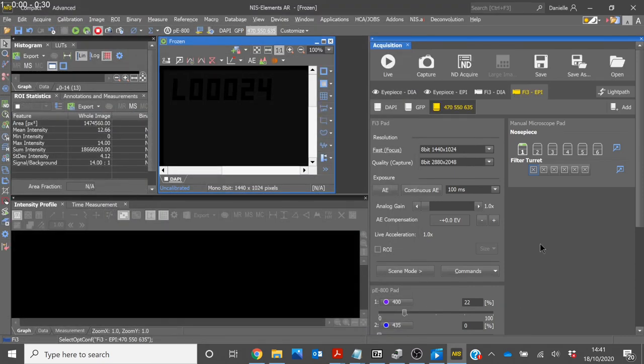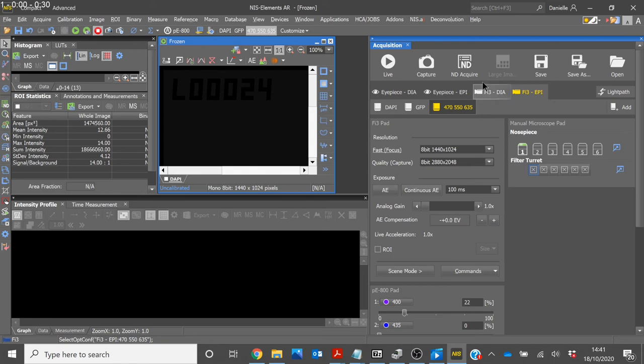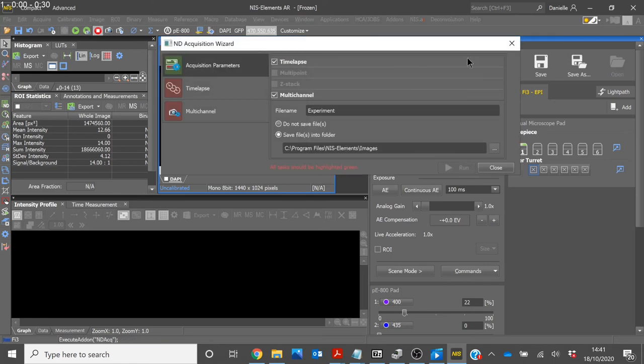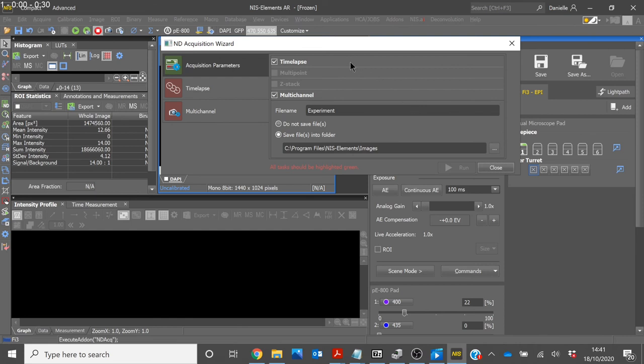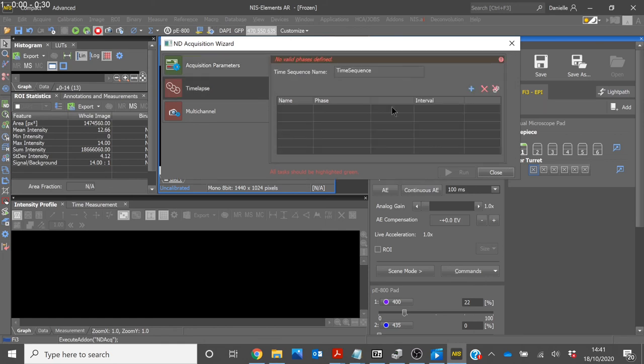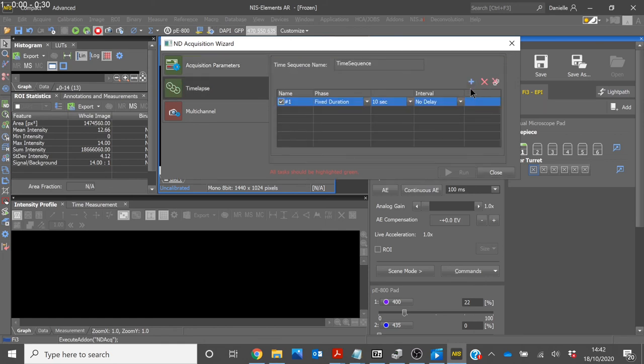Once you are happy with your optical configurations, you are now ready to run an experiment. To do this, click on ND Acquire. Here you can select the file name and the location under which you wish your images to be saved. As we are using a manual microscope, multipoint and Z stack options are not enabled. First select Time-lapse and add in your interval parameters.